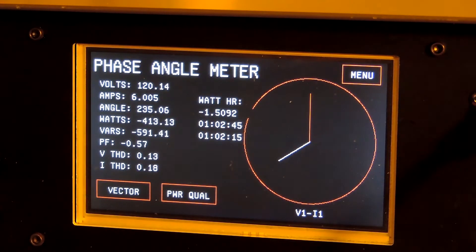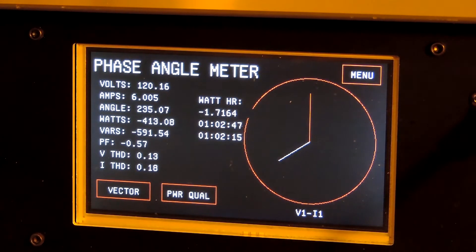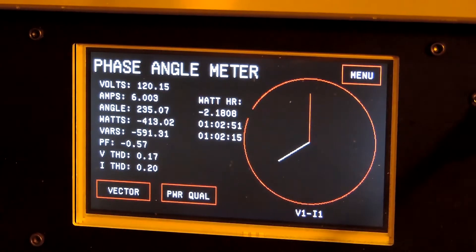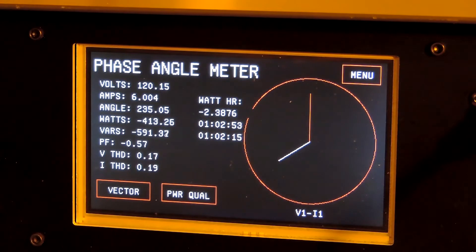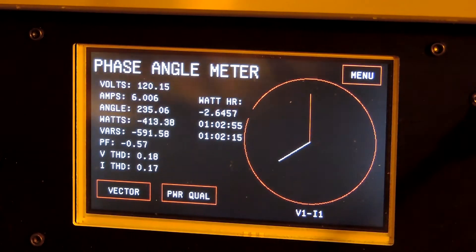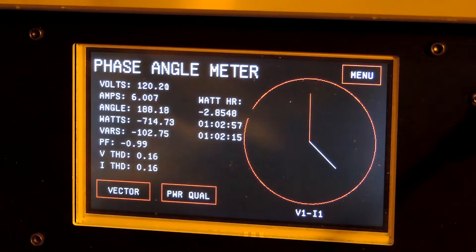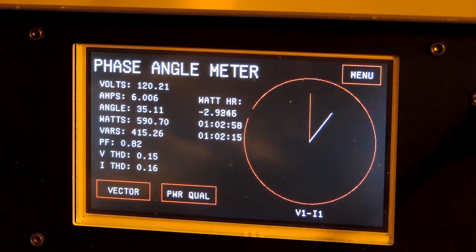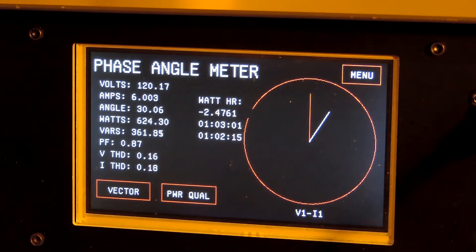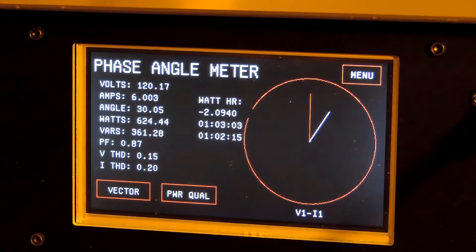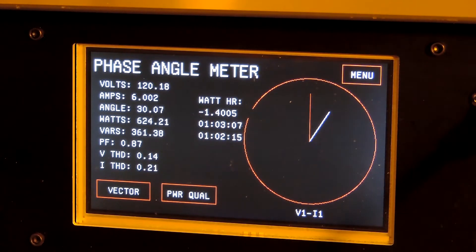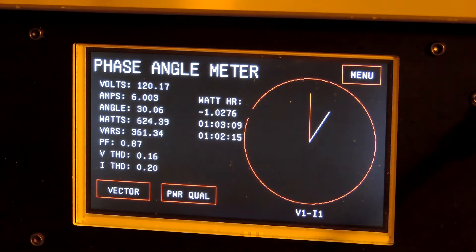The watts is reading negative because in the case of this particular angle, it's watts out. If I go to 30, it of course starts going down because it's now watts in. But that's a basic tour of this phase angle meter.